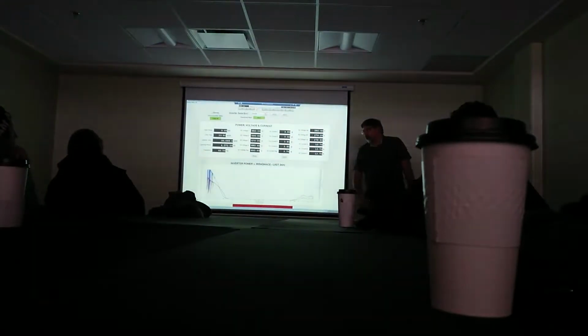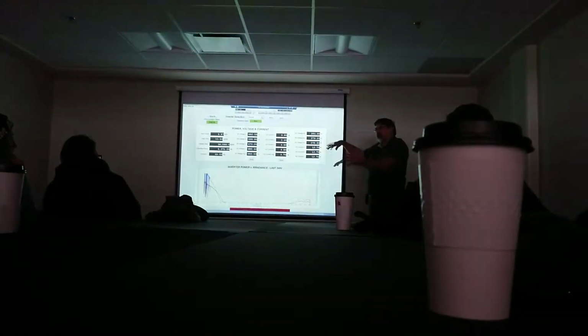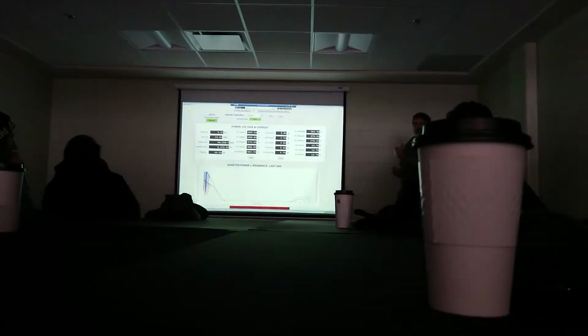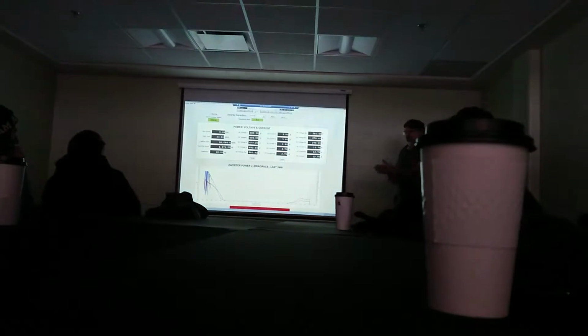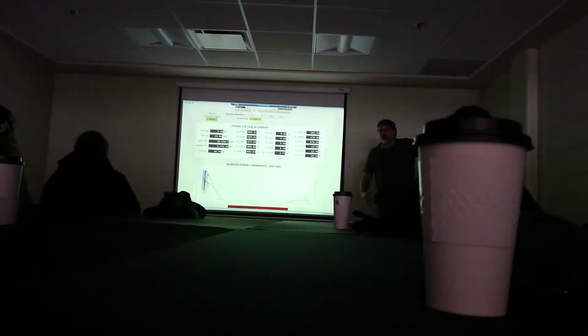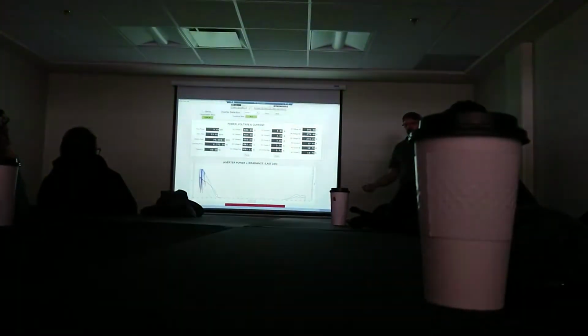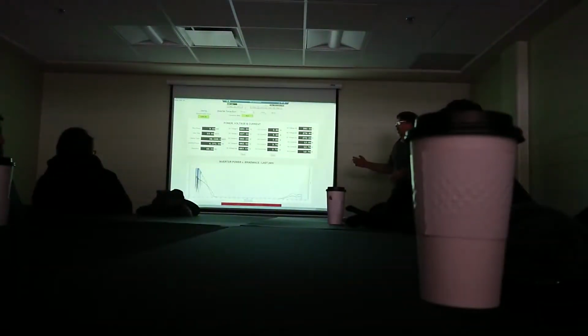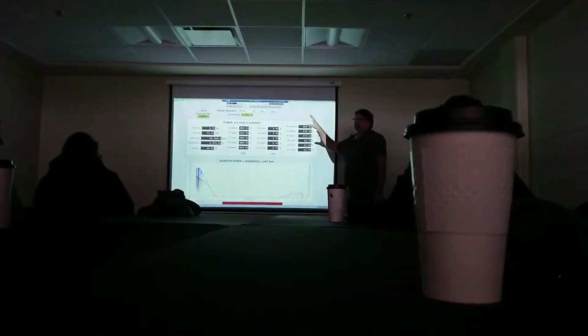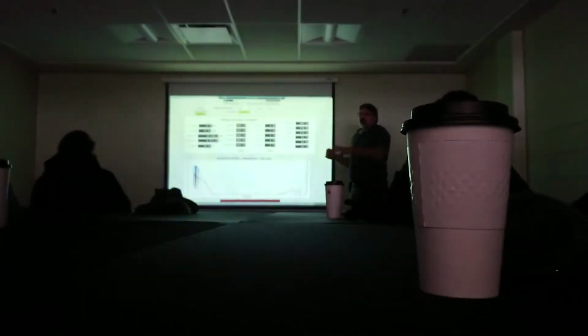But in trending, like that first graph we were looking at, that's what I use to see how well the system is working, and whether the set point I selected, like 600 kilowatts, is good. I can look at previous data and check whether I should have gone more or less aggressive. It also lets me compare the different inverters to see if they're all working. Trends let you see those kinds of things.